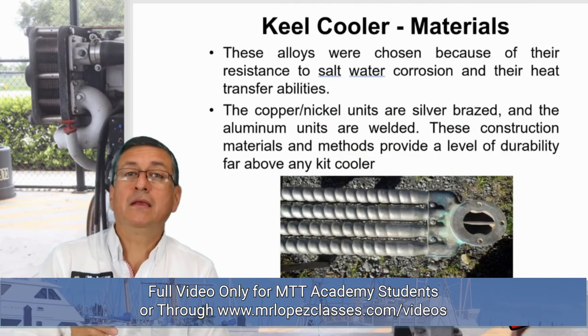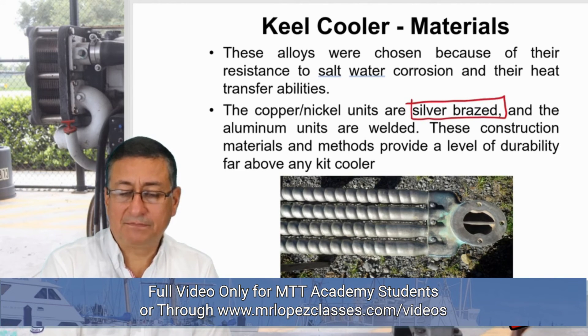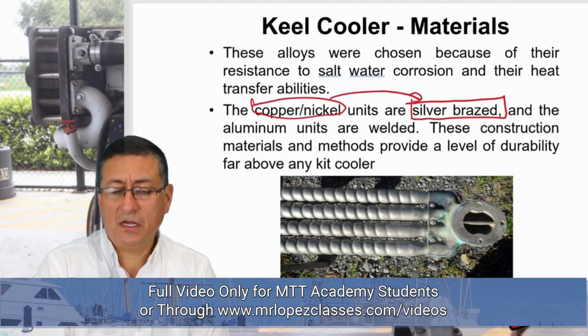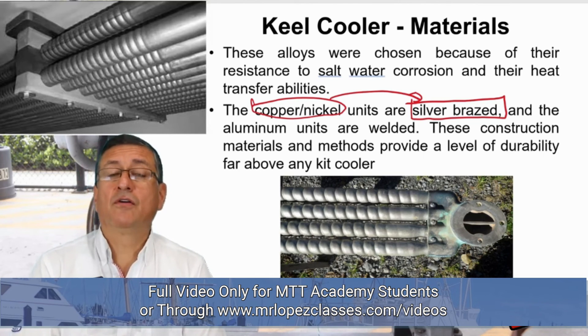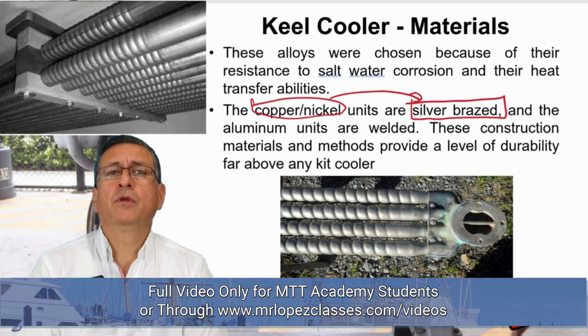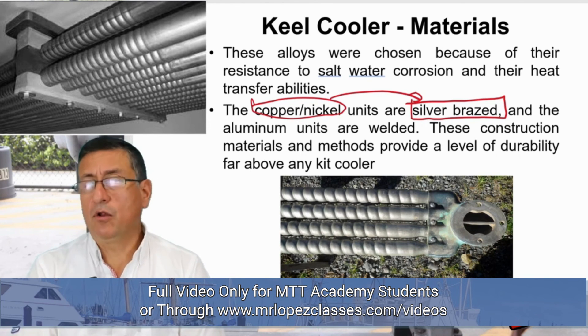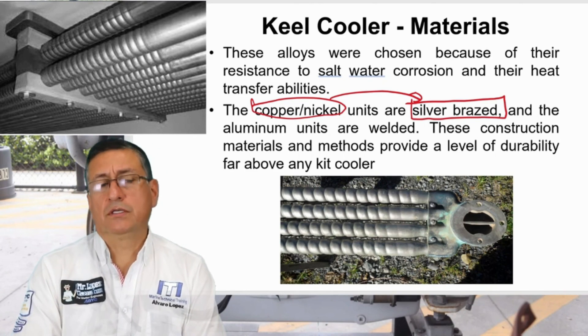The welding between those pipes is done with silver braze. The copper nickel units are welded with silver braze. There are also external radiators made in a special alloy of aluminum, and the welding in those alloys should be with pure aluminum. So there are external radiators for keel cooling systems in aluminum and external radiators for keel cooling systems fabricated in copper nickel alloys.